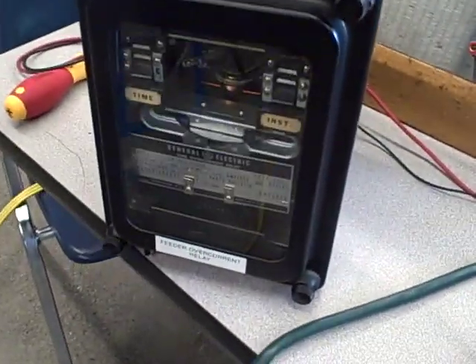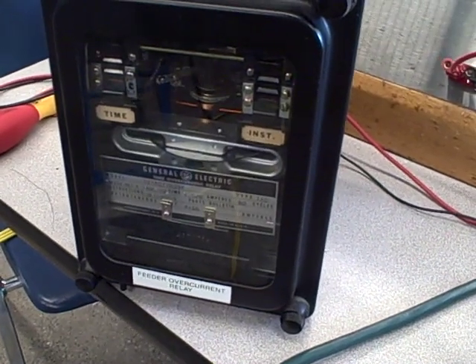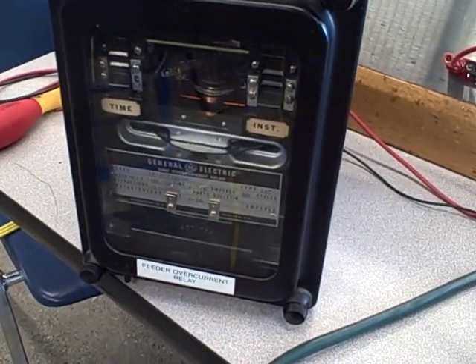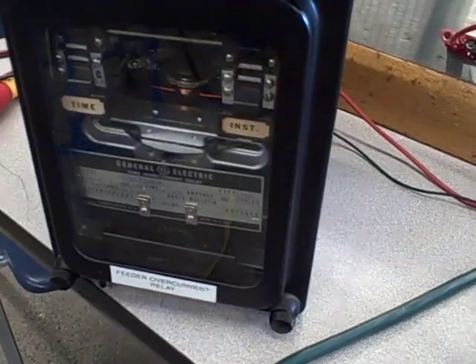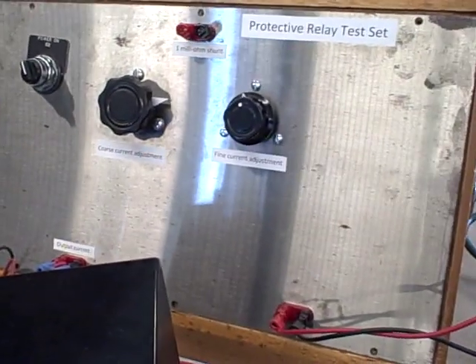What we're going to be doing here is a test on this time over current protective relay to see how many seconds it takes to trip the circuit breaker with a given amount of current set from our protective relay test set.